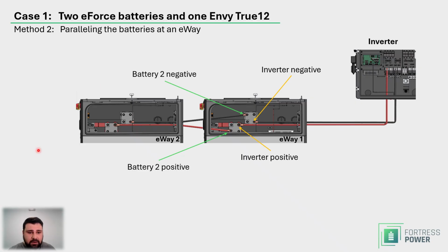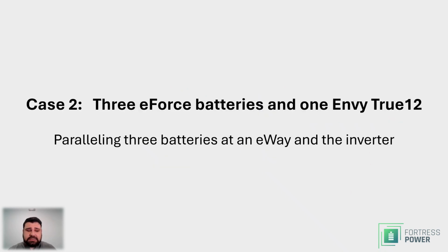Again, we avoided using an external bus bar, and this approach actually could be more useful in the field because you need less conduit length and less cable length, which saves you a couple of dollars and also a ton of time if you ask me. Next, we're going to switch to case 2: 3 eForce batteries and 1 Envy True12, paralleling 3 batteries at an eWay and the inverter.